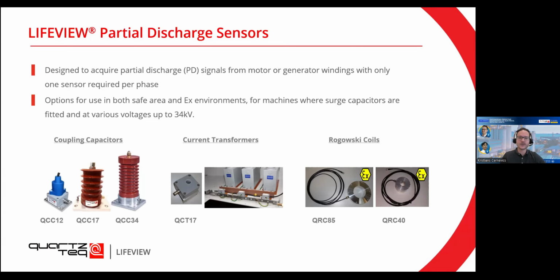And finally, Rogowski coils are specially designed to be used in the EX environment. A bit similar to the current transformers, it's an inductive source. You have an air core inside, you have a coil inside, and then once you see fast transients, so fast partial discharge happening, the Rogowski coil will convert it to the signal for the PDA2 or mobile kit to analyze.